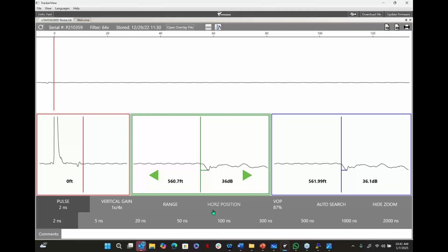So if you send me a waveform that you shot in a 100 nanosecond pulse width, I'm going to ask you to go back and shoot it in a 1 or a 5, because I'm not going to be able to see anything from here. That costs you more time. That costs the company another truck roll. So make sure you always know what your pulse width is. Start out small. The cool thing about the Springboks is that it shoots it all in one shot, and I will show you why that's an advantage here coming up.